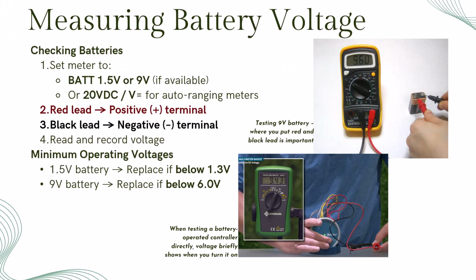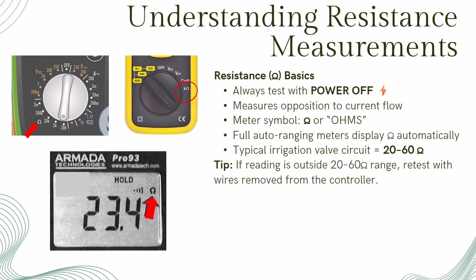To measure battery voltage, set your meter to the correct DC setting, either the battery test position or the 20 VDC for most meters. Place your red lead on the positive terminal and black lead on the negative terminal. Typical thresholds: if a 1.5 volt battery reads below 1.3 volts, replace it. If a 9 volt battery reads below 6 volts, replace it. Even a small voltage drop can affect the operation of battery-powered controllers or latching solenoids, so routine testing helps prevent system failure. When testing resistance, always remember, power off first.